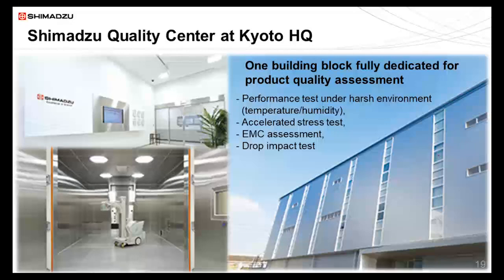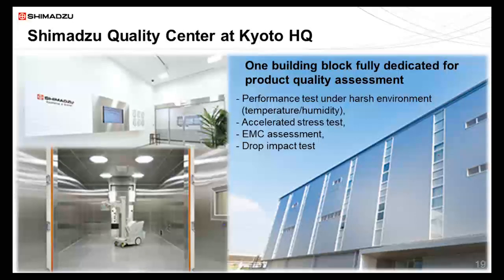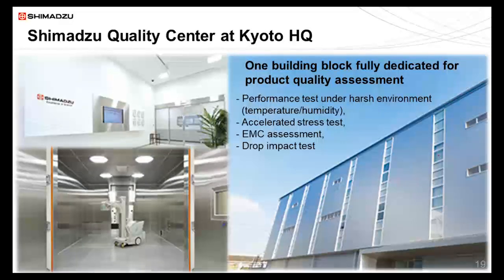So we've brought in our Q-TOF instrument in this metallic room where we can control the temperature very accurately. And we've done a 24-hour batch hourly measurement of the calibration standards, and we've shifted the temperature up by 3 degrees, and then down by 6 degrees, and then up by 3 degrees again, back to the original temperature. And this happened in 24 hours. This is an extreme case. You don't expect to see that much temperature fluctuation in a laboratory environment. But we've done this to see how temperature might affect our data.